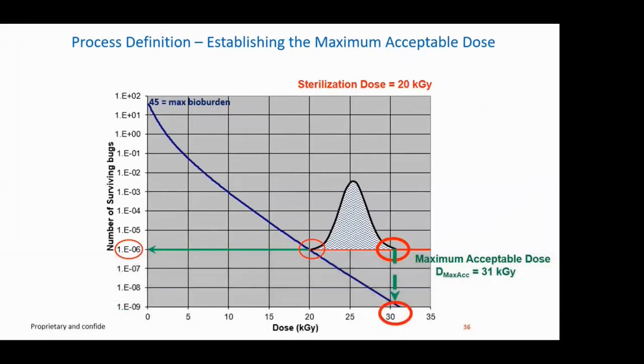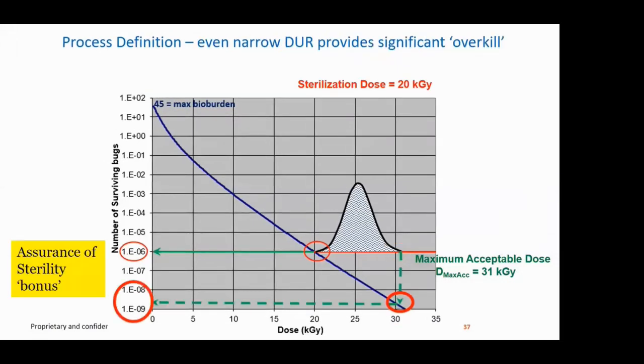I gave you one sterile assurance freebie earlier about the guidance on alternative SALs. This is really the second bonus on assurance of sterility. Even in a narrow dose distribution like that, going to 31 kilogray, the reality is you're always less than an SAL of 10 to the minus 6, down to close to 1 in a billion, not just 1 in a million, devices with one organism. So it puts into perspective the overkill nature of even radiation sterilization.